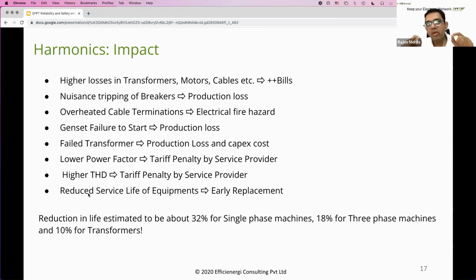But electronic equipment failure, I want to call that out. The electronic equipment, when I talk about drives, or anything which is AC to DC conversion, an SMPS, these are meant to operate in a harmonic rich environment. They are the ones who are themselves chopping the sine waveform. They are not going to get affected by harmonics. Let's be very clear. They are the culprits, if they were to be called that, generating these harmonics and really causing the current waveform to get distorted.